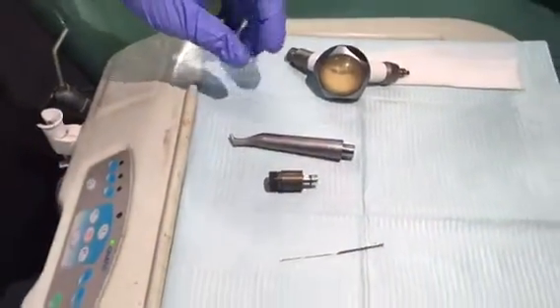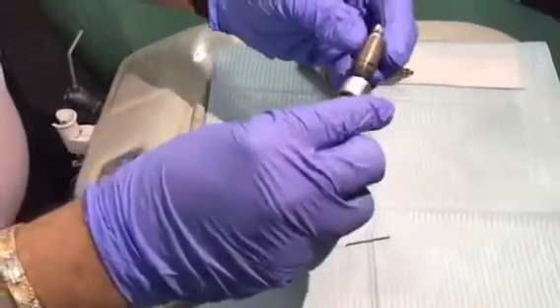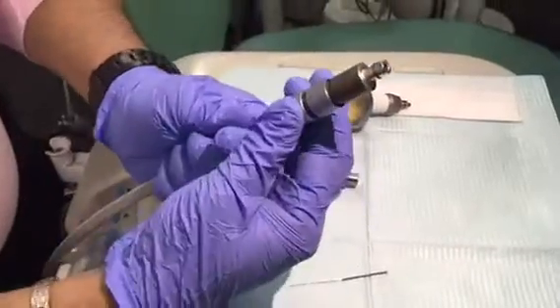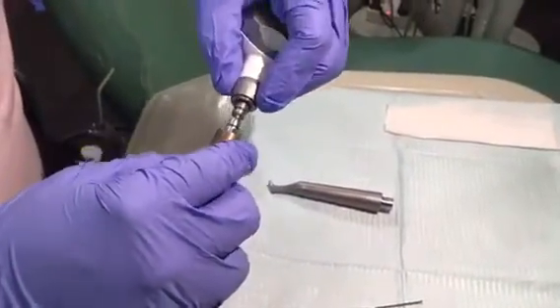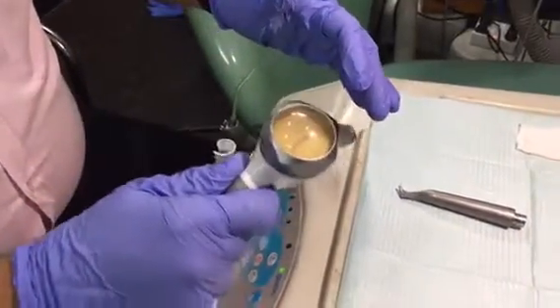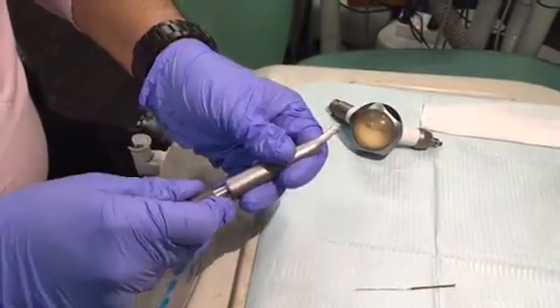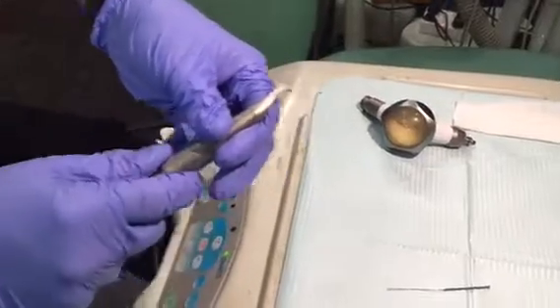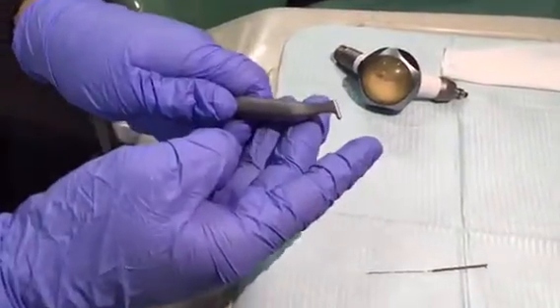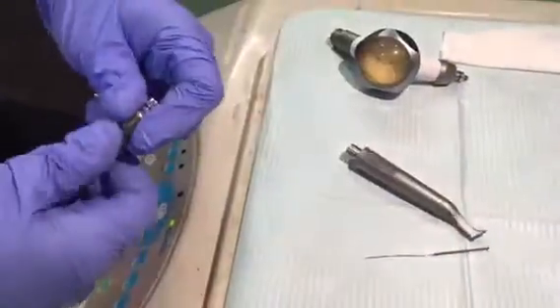You also get a coupling in your box. Attach the coupling to an air rotor point, switch off the water, then connect it to this end and clean it with your air rotor pressure. You can also connect it to this end and clean. Make sure that air is coming out from this portion — it should not be blocked.